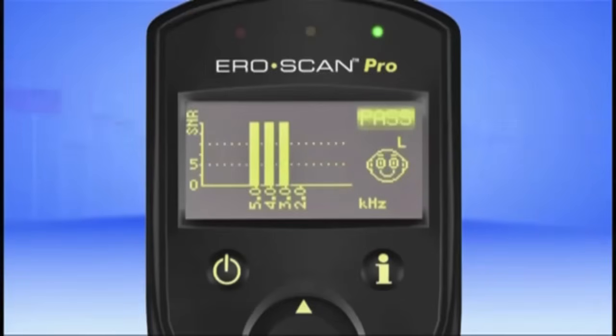A pass indicates the subject passed the screening test. A refer means that the subject should be referred for further testing. Please be aware that the Ero Scan Pro saves only the last test for each ear per test protocol. So, for example, let's say you tested a patient's left ear with protocol A. If you start another test on the left ear using protocol A, the previous results are erased and cannot be retrieved. Protocol A's right ear results and the results for other protocols remain unaltered.